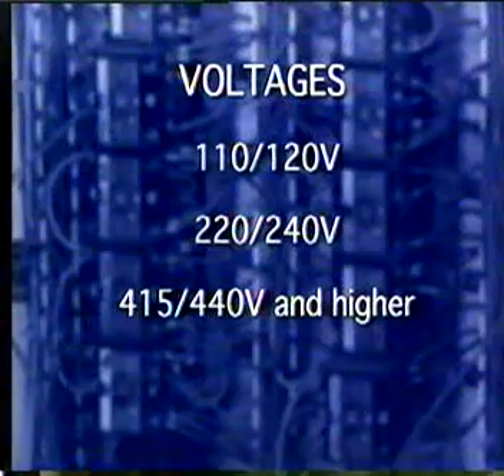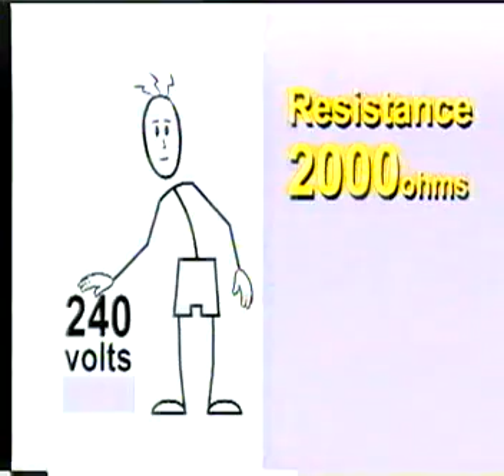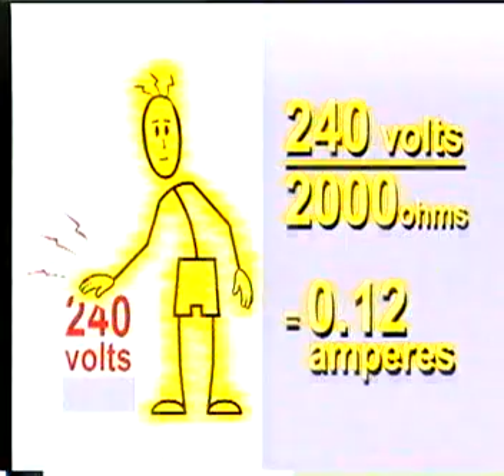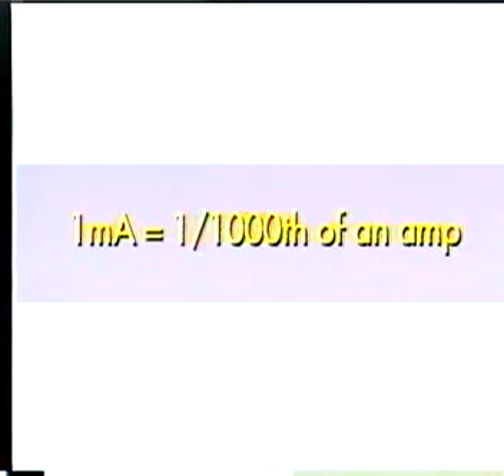For example, let's assume a person has a total resistance to electricity of 2000 ohms and touches a live part of a 240 volt circuit. The current they'd be exposed to is calculated by dividing voltage by resistance: 240 divided by 2000 equals 0.12 amperes, or 120 milliamps - 1 milliampere being 1/1000th of an amp.